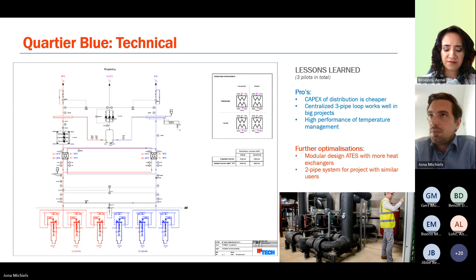Now, the biggest thing that we learned, or the biggest advantage of this type of system, is that it's a very low temperature, so you can combine heating and cooling demand very easily from the same distribution channels, and you can save a lot on capex as well, since the distribution can be completed in PE, where in higher temperature distribution networks you would still use steel, and you would need to insulate the distribution channels as well. Whereas if we install a neutral net in the ground, you don't really need to insulate it, simply because you have very, very low heat losses, because the difference in temperature between the piping and the underground is almost zero.